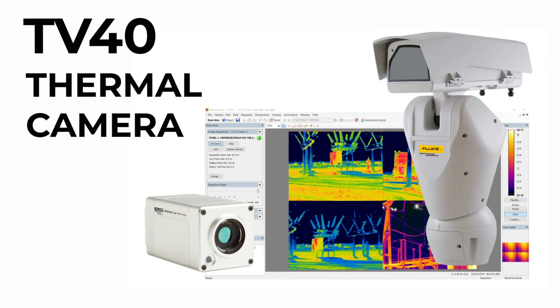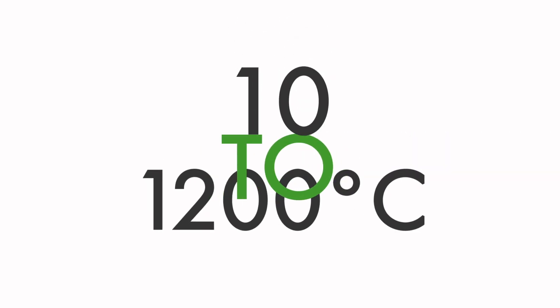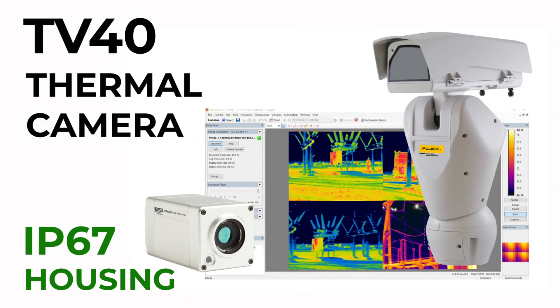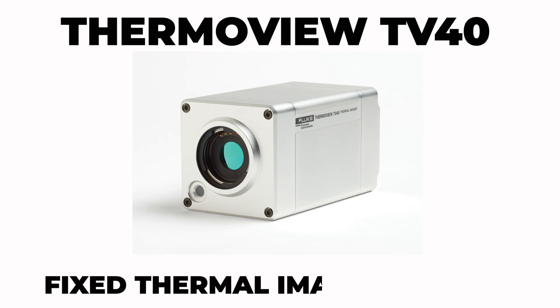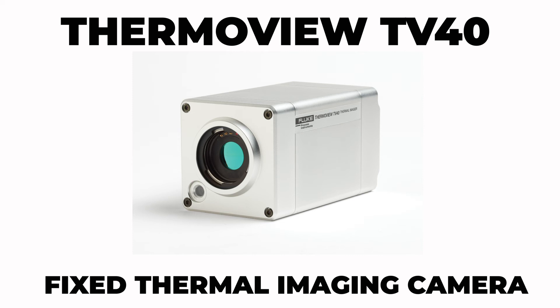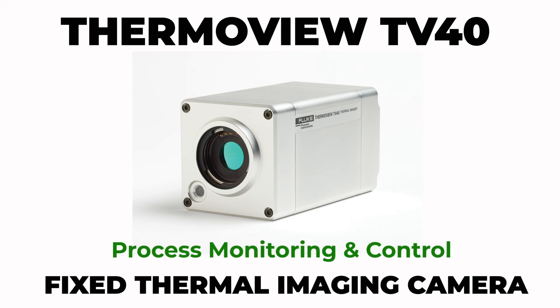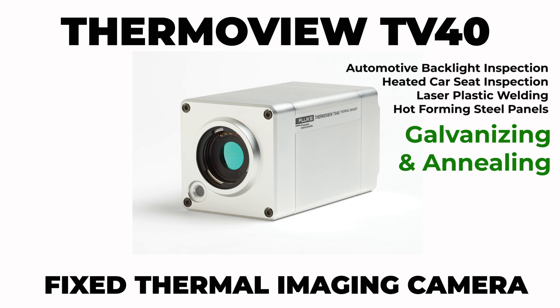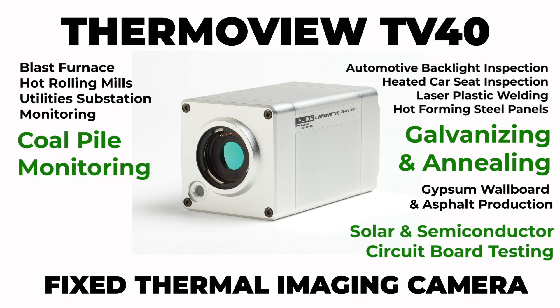The rugged TV40 thermal camera lets you visualise the temperature data you require anywhere in your process with reliable high quality resolution. It has a temperature range of 10 to 1200 degrees Celsius. The IP67 housing guarantees long-term thermal imaging in the harshest environments. It features simultaneous infrared and visible sighting to quickly locate potential problems. Working alongside the ThermoView software enables you to take control of multiple parts of your process like never before. The ThermoView TV40 fixed thermal imaging camera is ideal for process monitoring and control, quality pass-fail checks and on-site safety, including applications such as galvanising and annealing, solar and semiconductor circuit board testing, coal pile monitoring and waste incineration.